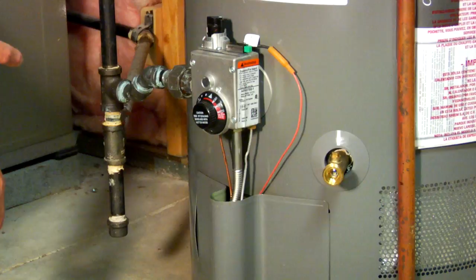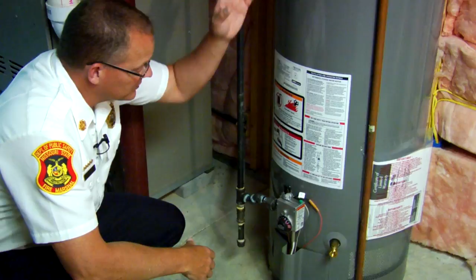One of the other things you want to look for is down in the burner unit. In the burner unit, you can look around the edges of this cover or the interior cover for that same soot buildup. If you have soot buildup, it could be that you have a leaky water heater that's creating an inefficient burn, or you could have the same thing with the flue gases pushing down into the burner and pushing carbon monoxide out into the room.